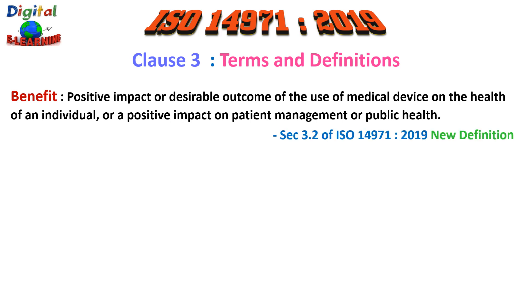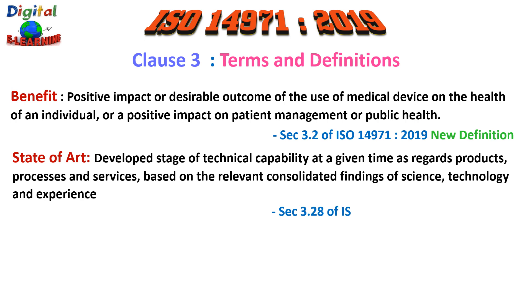Three new terms have been added under clause 3, terms and definitions, in the revised 2019 edition. The first is 'benefit,' defined as the positive impact or desired outcome of using a medical device on the health of an individual, or the positive impact on patient management or public health. Examples include faster recovery, more accurate diagnosis, better public health care, or more complete recovery. The second is 'state of the art,' meaning the developed stage of technical capability at a given time, as regards products, processes, and services, based on relevant consolidated findings of science, technology, and experience.